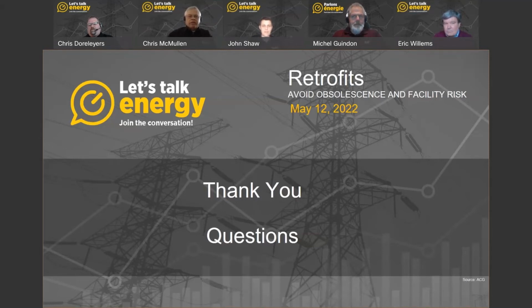The first thing we need to do when looking at closed transition or peak shaving is a connection agreement assessment through Hydro. Hydro is the first to say whether you can go ahead and close transition to the grid, or no, it must remain within the 100 millisecond limit, or yes, you can base load your unit to the utility and remain that way as long as you want. Adding to that, if we set up the unit for peak shaving or global adjustment, the Ministry of Environment gets involved, and we may have to add scrubbers or SCR to the genset to clean up emissions so it can run for non-emergency use.